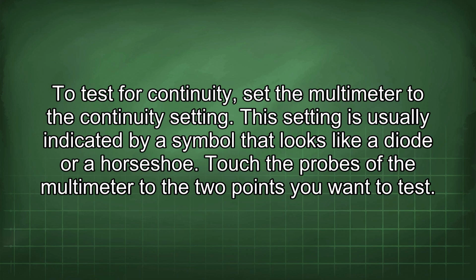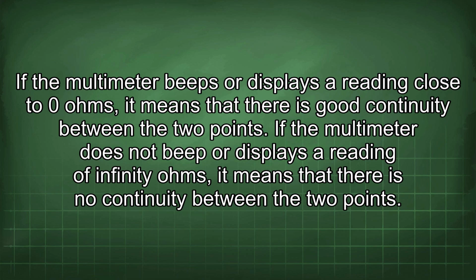Touch the probes of the multimeter to the 2 points you want to test. If the multimeter beeps or displays a reading close to 0 ohms, it means that there is good continuity between the 2 points. If the multimeter does not beep or displays a reading of infinity ohms, it means that there is no continuity between the 2 points.